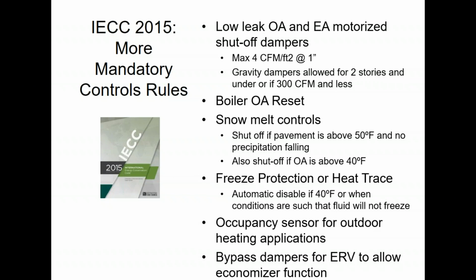And then whether you have a wheel or plates or whatever, you open up the bypass dampers to bypass the air around the ERV so you're not paying for the extra static pressure drop penalty. You do not want to operate an ERV in an economizer situation because it's actually going to recover energy from the space, which is going to be detrimental to what you're trying to do. So you need to disable the ERV and provide an economizer function using bypass dampers.